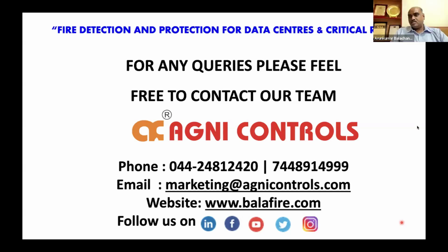Manik Gupta is asking which extinguisher is recommended for a data center having 50 servers. If you talk of extinguishers, then you can very well go in for carbon dioxide, because any foam or dry chemical powder, the ABC powder, is going to harm the servers. So the best handheld extinguisher is going to be carbon dioxide. Or you can go in for a chemical-based portable extinguisher if you don't want to use carbon dioxide in your facility.